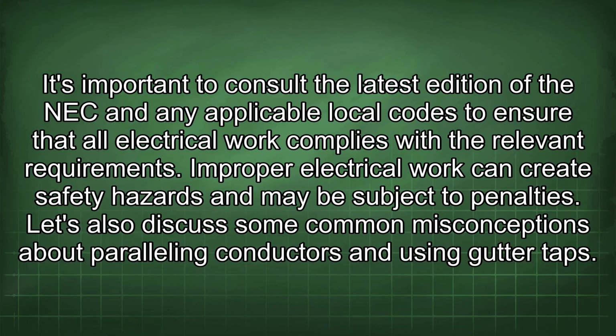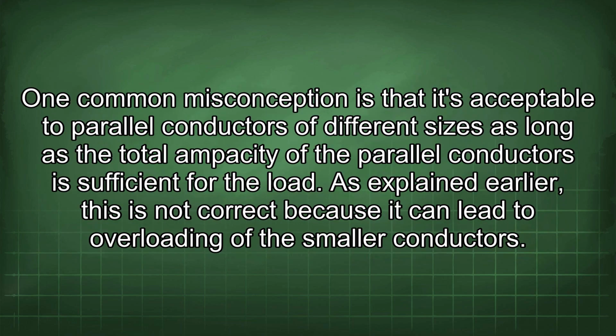Let's also discuss some common misconceptions about paralleling conductors and using gutter taps. One common misconception is that it's acceptable to parallel conductors of different sizes as long as the total ampacity of the parallel conductors is sufficient for the load. As explained earlier, this is not correct because it can lead to overloading of the smaller conductors.